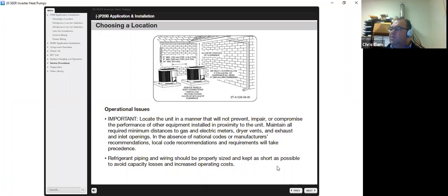It is important to locate the unit in a manner that will not prevent, impair, or compromise the performance of other equipment installed in proximity to the unit. Maintain all required minimum distances to gas and electric meters, especially dryer vents and exhaust and inlet openings. In the absence of national codes or manufacturer recommendations, local codes will take precedence. It is important refrigerant piping and wiring should be properly sized and kept as short as possible to avoid capacity loss and increased operating costs.